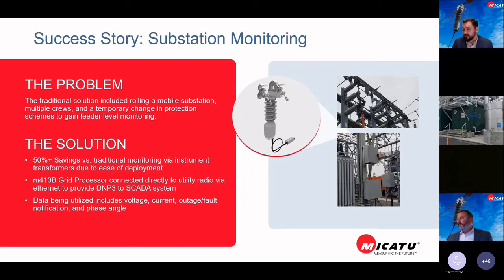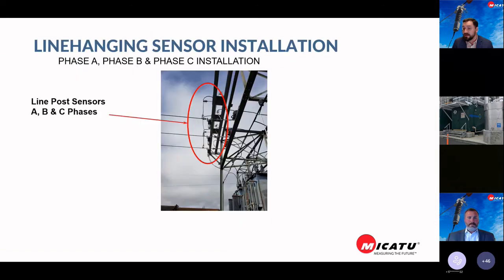We can basically just replace a PT with our sensor by quickly hanging it on the line, offering reliable and accurate sensing without the additional cost. In this picture, we hung three sensors - I was there that day - and we did this in about six hours from top to bottom, including a safety meeting at the beginning. So it's a fairly quick effort to install these sensors.